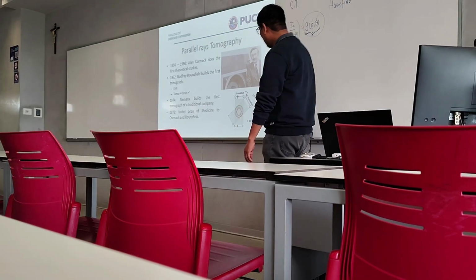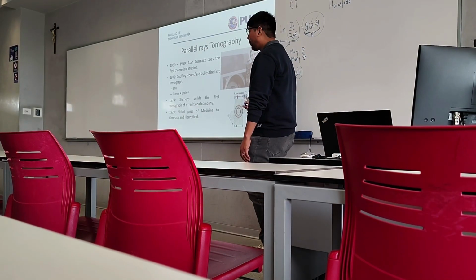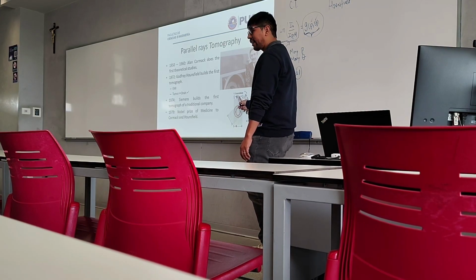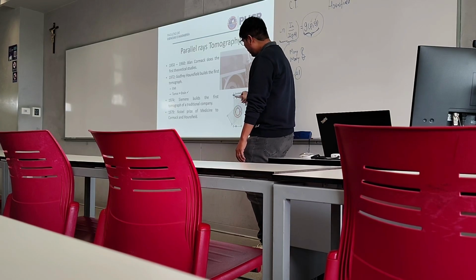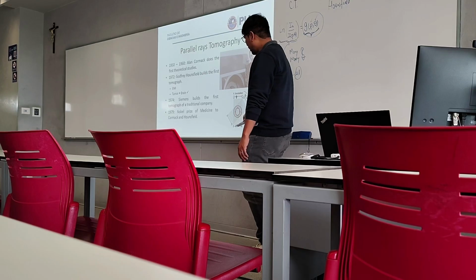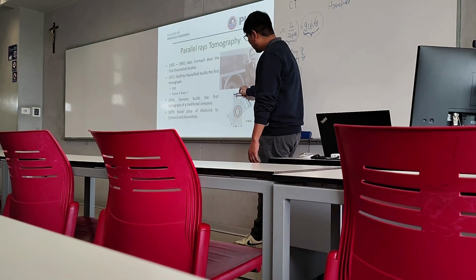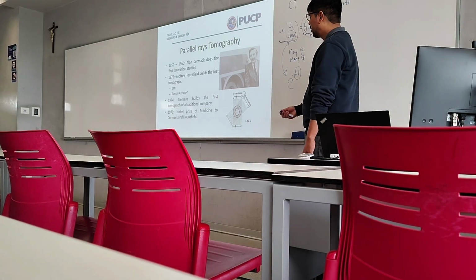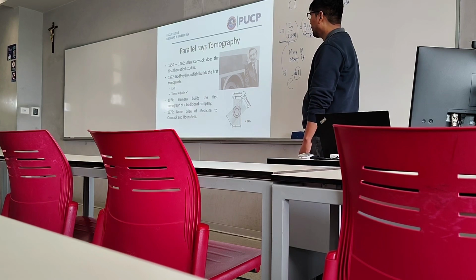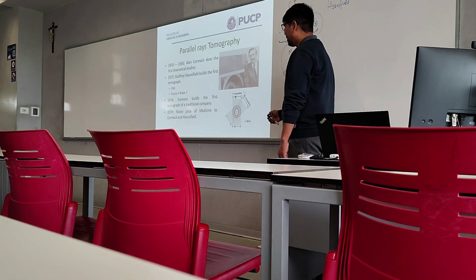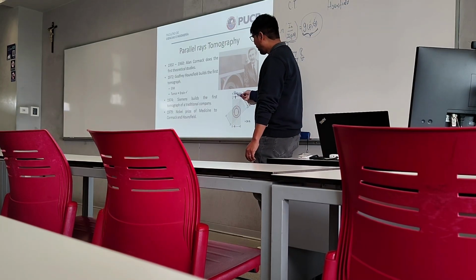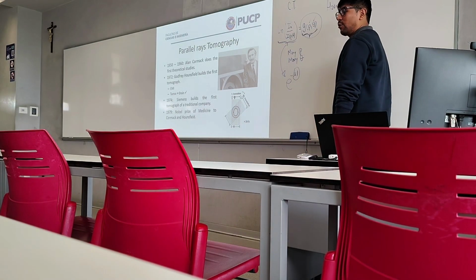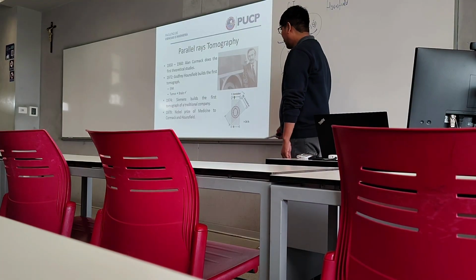Something more here is that in the past there was a translation of the sources and detectors. There was one source, one detector, and they translate both at the same time to calculate parallel lines. In current devices, there is not this translation process. All parallel rays are calculated simultaneously, which makes it much faster.